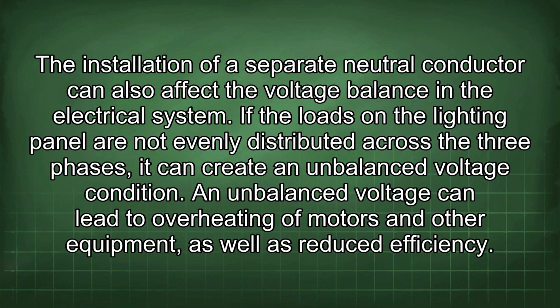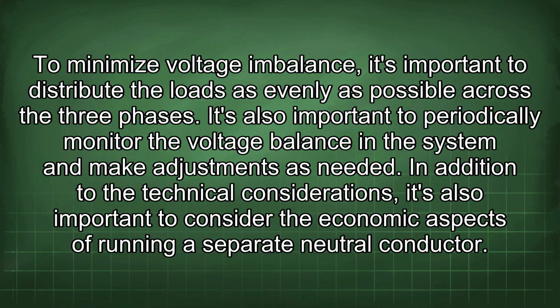The installation of a separate neutral conductor can also affect the voltage balance in the electrical system. If the loads on the lighting panel are not evenly distributed across the three phases, it can create an unbalanced voltage condition. An unbalanced voltage can lead to overheating of motors and other equipment, as well as reduced efficiency. To minimize voltage imbalance, it's important to distribute the loads as evenly as possible across the three phases. It's also important to periodically monitor the voltage balance in the system and make adjustments as needed.